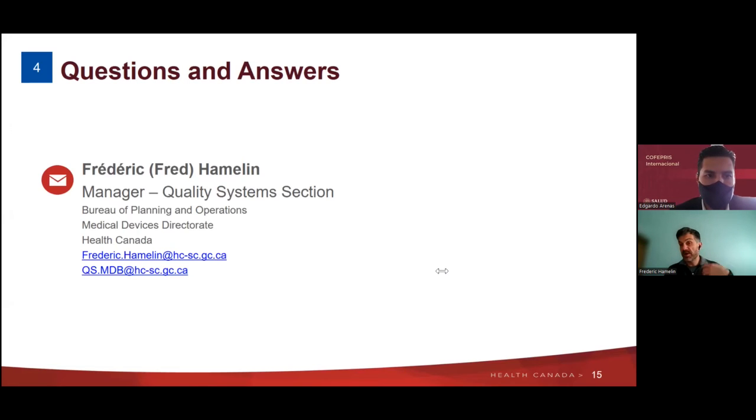The other thing we did, again, to help facilitate the transition, is that we allowed manufacturers to be very flexible in their approach, to say, well, I'm not going to start initially with a new MDSAP certification. So I will start midway through an existing process of doing MDSAP through the surveillance until I get to the recertification and then the certificate, which added a few years in effective transition, in the sense that we didn't have on file an MDSAP certificate for every manufacturer until last year, because of that extension of those surveillance transitions.